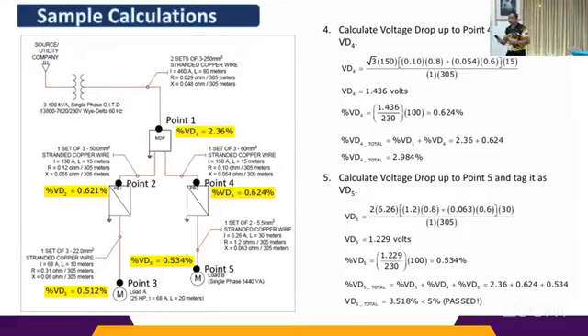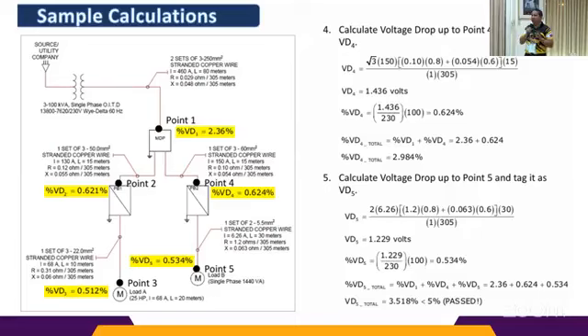Next. The same process applies at point 4, at panel board 2. At point 4, voltage drop 4 is 1.436 volts, so the percent voltage drop is 0.624%. The total voltage drop 4 is 2.36 plus 0.624, which comes to 2.984%. Now step number 5, calculate the voltage drop up to 5, VD5. Again, substitute the given values from our diagram. Voltage drop 5 is 1.229 volts, so the percent voltage drop 5 is 0.534%.